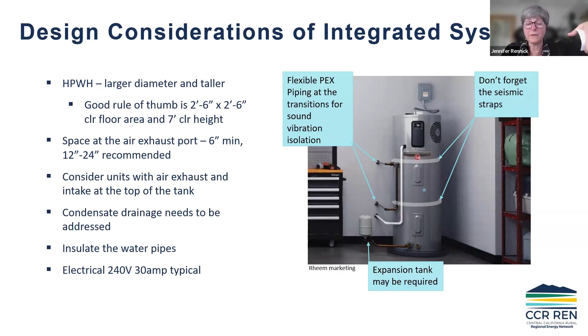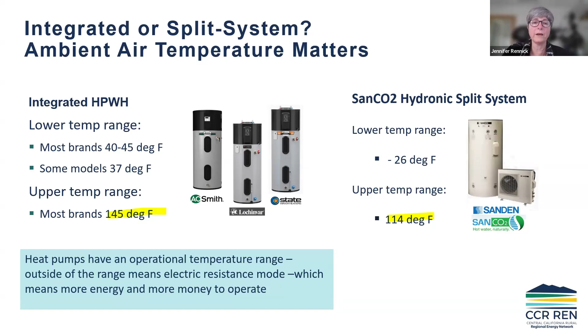They do have an operating temperature range. On the integrated type, which means you've got your heat pump on top and the big tank of water down below, the brands with the widest operation range only will operate down to 37 degrees Fahrenheit. So not very cold, and certainly above freezing. So be careful how you place these, but the upper range goes quite high at 145 degrees. What this operation temperature basically means is that if it goes outside these ranges, the unit goes into electric resistance mode, which uses more energy and costs more money to operate. And then there are split systems. Again, it's similar to a split system on your space conditioning, but that upper temperature range is 114 degrees. So the Sanden or similar could be appropriate.